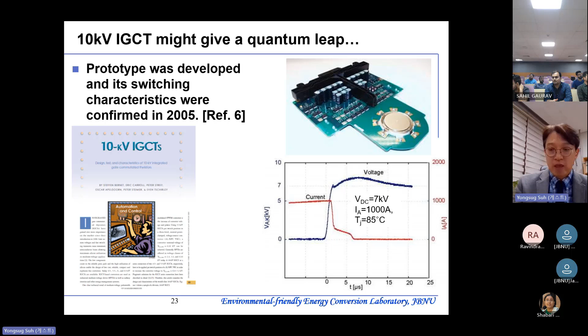3-level NPC employing 6.5 kV IGBT or IGCT have been the most common choice up to 7 MW. That was okay, but now we have discovered a lot of application fields such as wind turbine and grid following and grid forming inverters requiring more than 7 MW. A 5-level design seemed like too much, so why not develop a 10 kV IGCT so that we can easily cover drive systems more than 7 MW. That was the biggest motivation for me and the ABB team to develop the 10 kV IGCT.